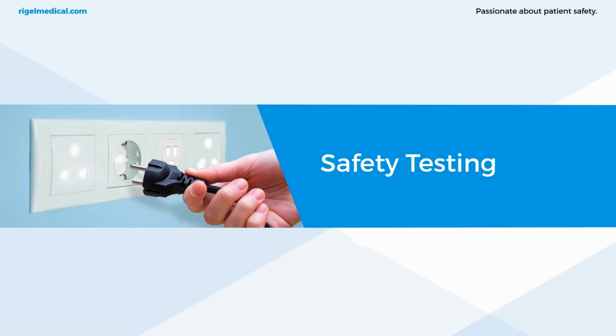So electrical safety testing in healthcare organisations is an important practice. It should be guaranteeing that everyone within that facility is safe. That's clinicians, visitors, and any vulnerable patients. The primary safety purpose is just to prevent any patient, operator, visitor being exposed to currents that are not part of the operational device. Anything outside of the operational device, which we talk about as leakage currents, so those are non-functional currents, are what we're trying to avoid and what we're trying to limit exposing any individual to.